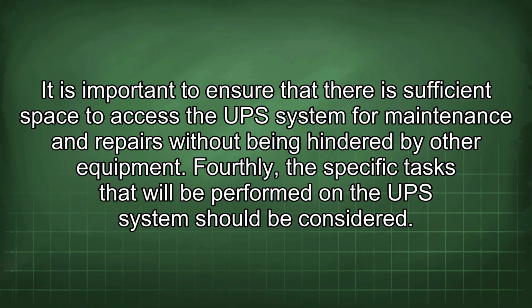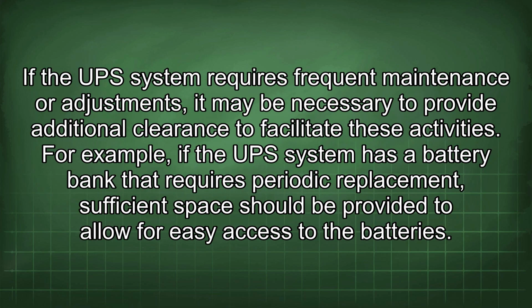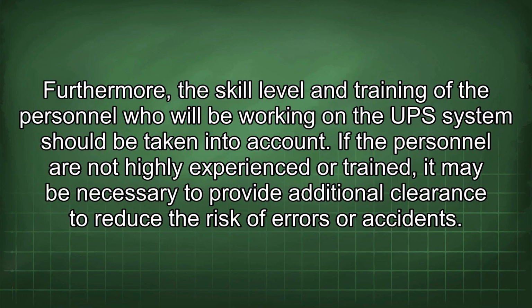Fourthly, the specific tasks that will be performed on the UPS system should be considered. If the UPS system requires frequent maintenance or adjustments, it may be necessary to provide additional clearance to facilitate these activities. For example, if the UPS system has a battery bank that requires periodic replacement, sufficient space should be provided to allow for easy access to the batteries. Furthermore, the skill level and training of the personnel who will be working on the UPS system should be taken into account. If the personnel are not highly experienced or trained, it may be necessary to provide additional clearance to reduce the risk of errors or accidents.